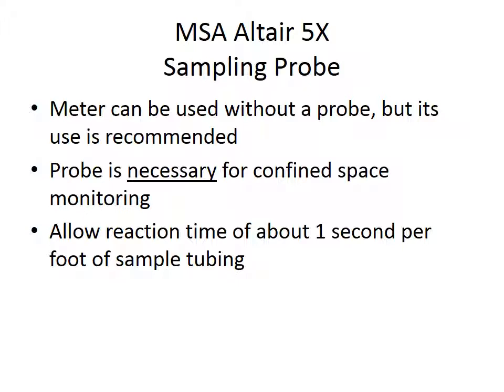So, the sampling probe. The meter can be used without the probe, but its use is recommended. Okay, and we'll talk about that here in a second. The probe is absolutely necessary if we're dealing with a confined space monitoring situation. I know this isn't really a confined space discussion, but the reason we need to use that probe in those situations is because when you sample a confined space, you need to sample at the bottom of the space, the middle of the space, and the top of the space, and the probe is really the only way to do that.